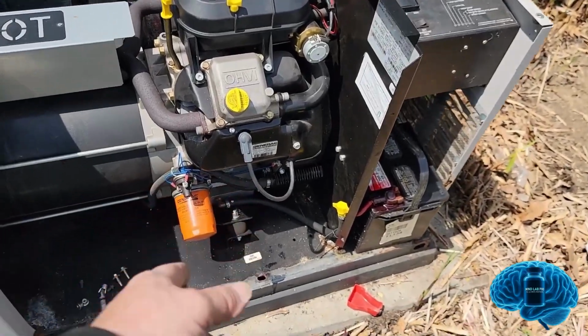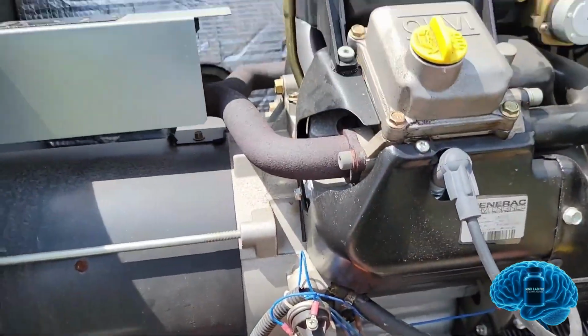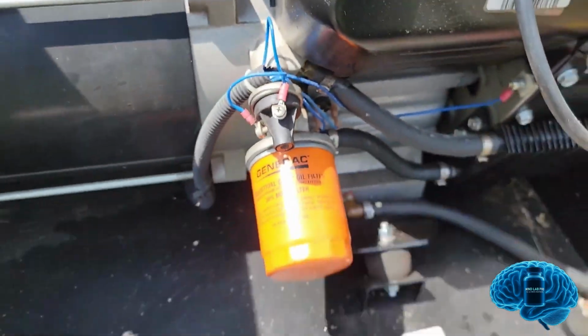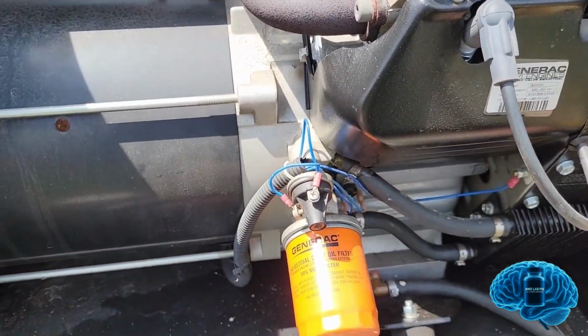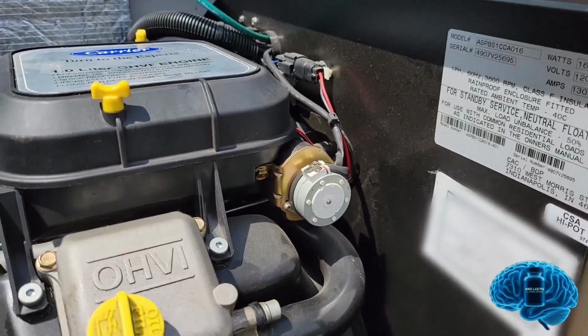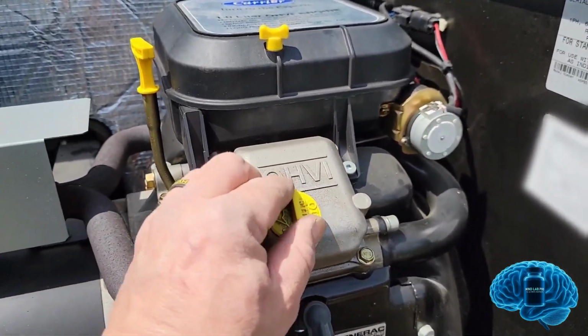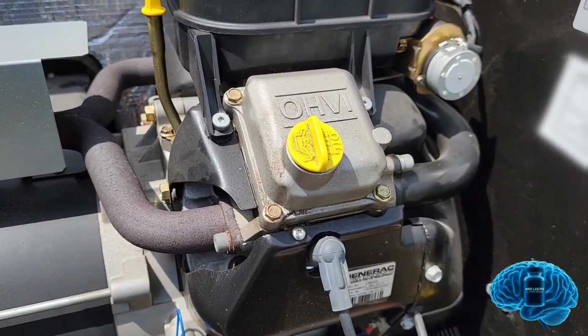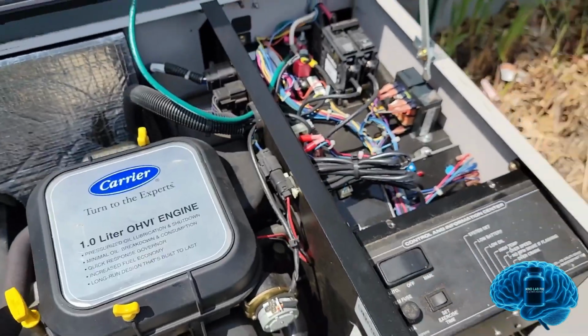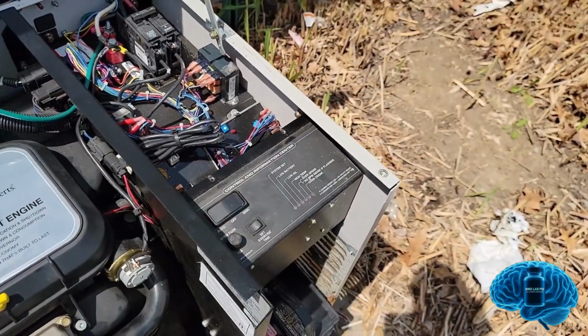You've got an oil pressure safety switch here that can go out. You've got a temperature switch down here on the bottom. Some of these are normally closed circuits, some are normally open. You've got your servo here—I haven't had too many of those fail. I've had idiots leave the cap off and lose the oil all over the place. That can happen. Those are some of my main things, along with the voltage regulator failing.